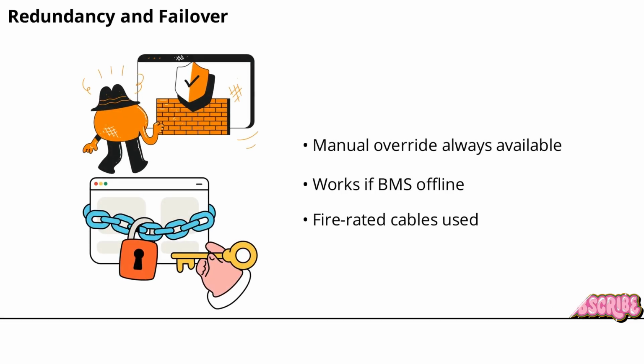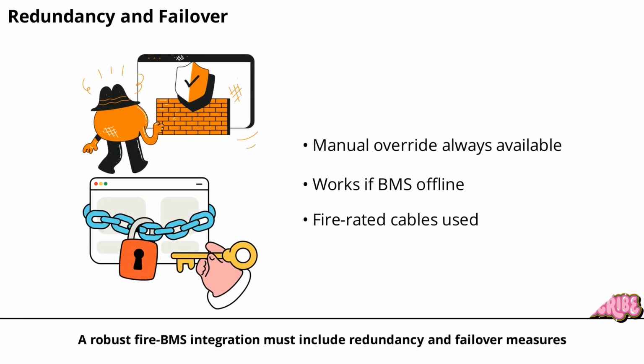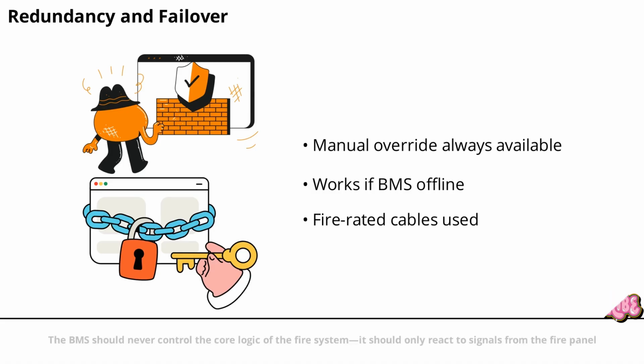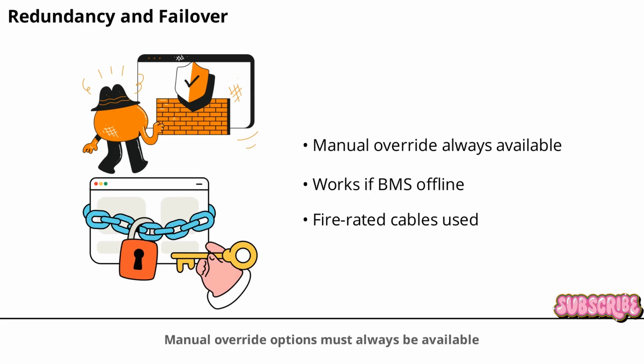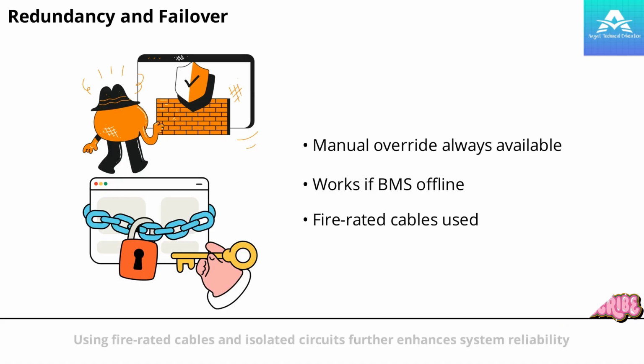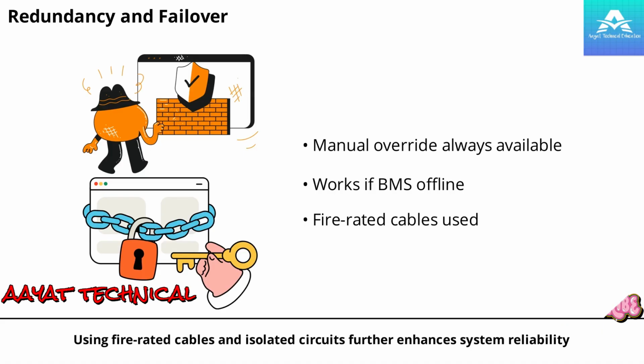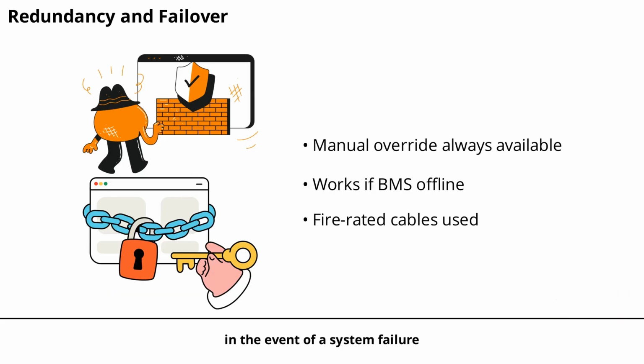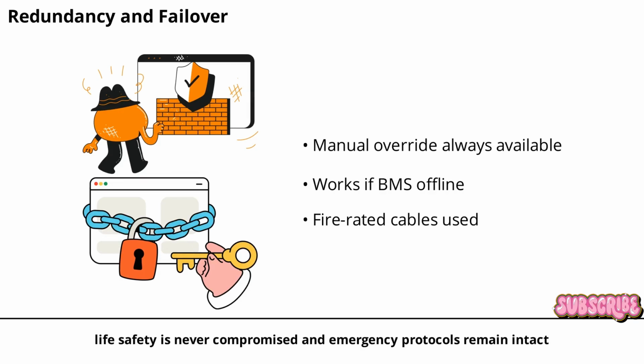A robust fire BMS integration must include redundancy and failover measures. The BMS should never control the core logic of the fire system, it should only react to signals from the fire panel. Manual override options must always be available, and the fire integration should function even if the BMS is offline. Using fire-rated cables and isolated circuits further enhances system reliability. These precautions ensure that, in the event of a system failure, life safety is never compromised and emergency protocols remain intact.